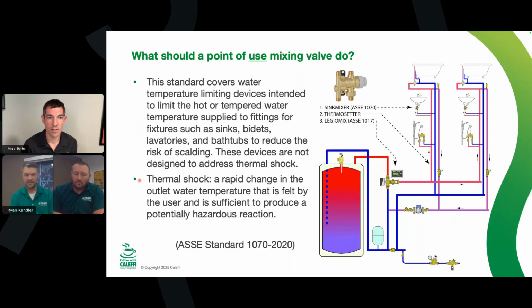Thermal shock doesn't have to be hot water, you can be shocked or surprised by cold water too. Say you're at a hotel in the shower, and mop sinks are notorious for this in public spaces, where janitors tend to put a little shut-off valve on the hose connection at the faucet and leave both hot and cold open. If you don't have check valves internally or on either of those lines, you're opening yourself up to flow from hot to cold or vice versa, depending on how that pressure is balanced.